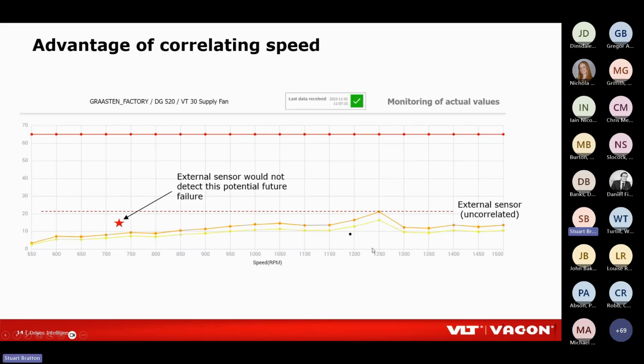particular system. If we were to put an external vibration monitoring sensor on this application, we might have to set it up so that it didn't generate a warning unless we exceeded something like 21 or 22 millimeters per second of vibration. But in this case, if we were running the fan at 725 RPM and the vibration increased to 15 millimeters per second, then our external sensor just wouldn't throw that up as a problem at all. It's only going to detect a problem when we exceed 22 millimeters.